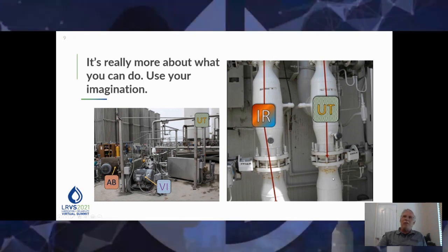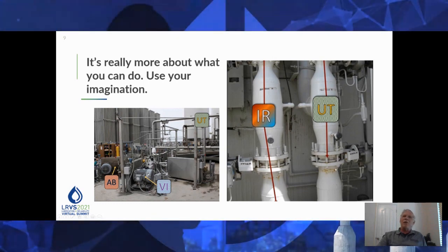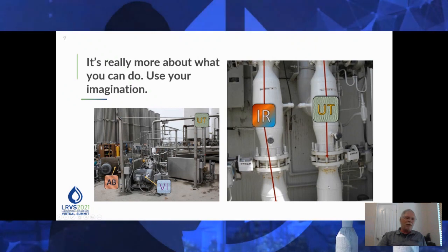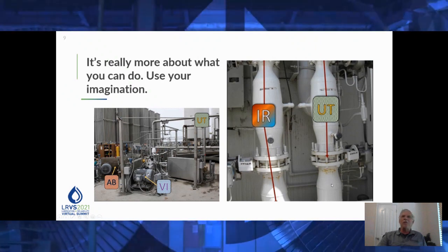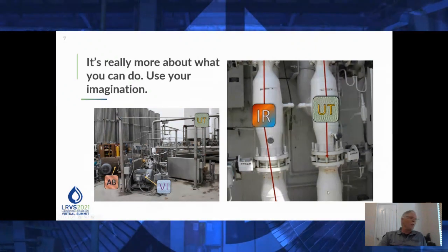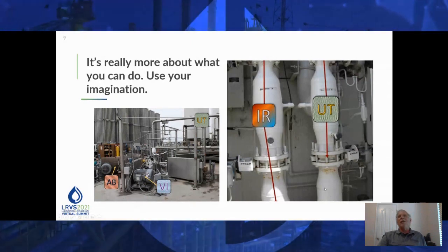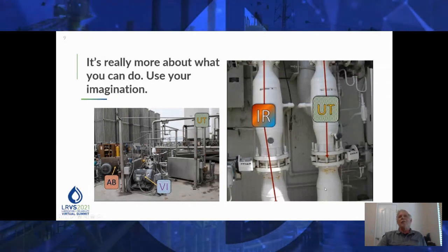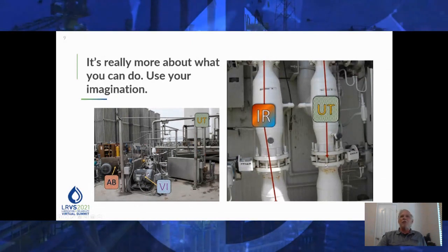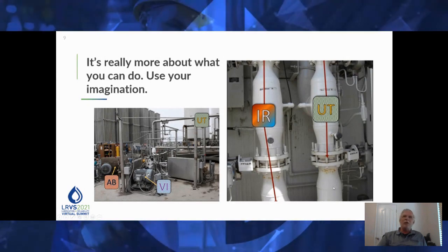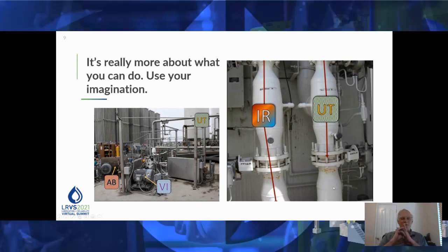Same thing we did on the other side. The infrared didn't show anything, but what the hell—let's put the infrared survey meter and the ultrasonic noise kit on there. And sure enough, the valve on the top was open, the valve on the bottom was supposed to be closed, but we had leakage through there.